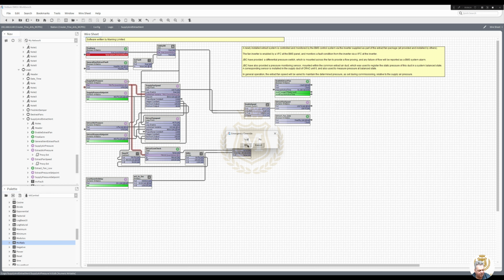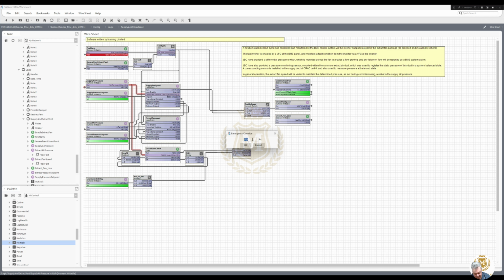749. So 750, take away that. So it's got to be below 700 for that to kick in. Actions, emergency override. 699, that should kick in, which it does.